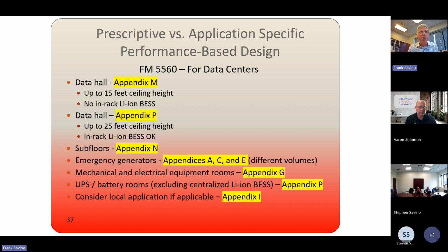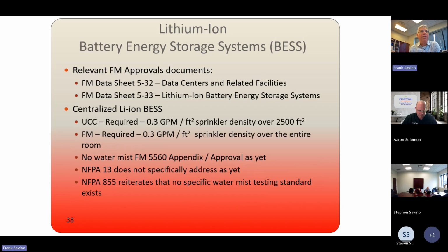Subfloors, Appendix N. Emergency generators, mechanical, electrical equipment rooms, so your high voltage electrical rooms, Appendix G. UPS battery rooms, Appendix P, like we said, and there is a local application also for, say, machinery spaces. You can do either total flood or local application with water mist. Local application means that you're discharging the water mist right onto the hazard areas that are expected to burn. Like equipment. Yes.